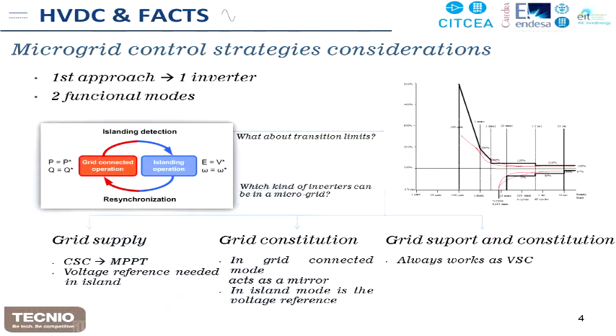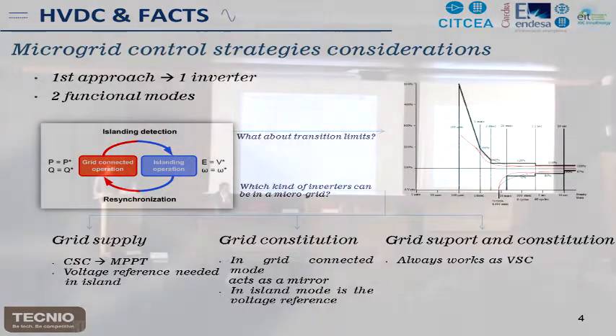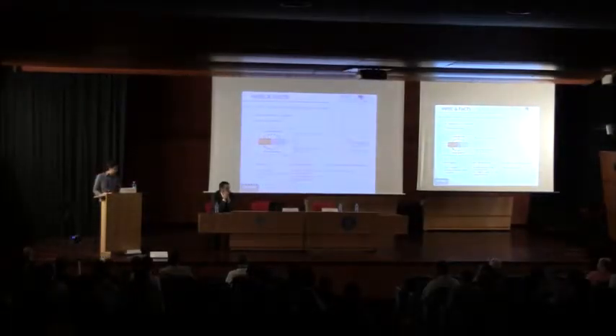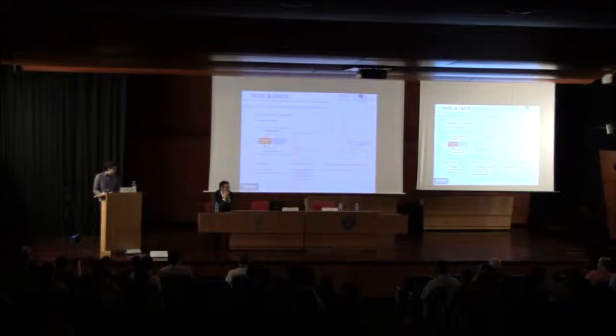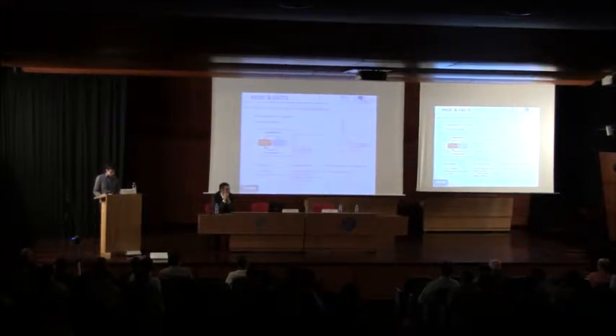Then another possibility is the grid constitution inverters, which are voltage source converters that control the voltage at their output. When they are connected to the grid, they act as a mirror, so there is no exchange of energy between the grid and the storage system. But in island mode, they are the voltage reference for other converters, such as the grid suppliers.